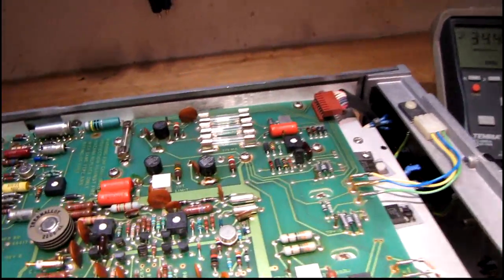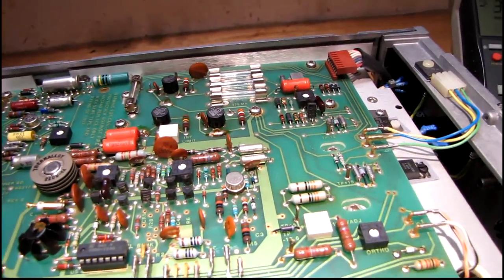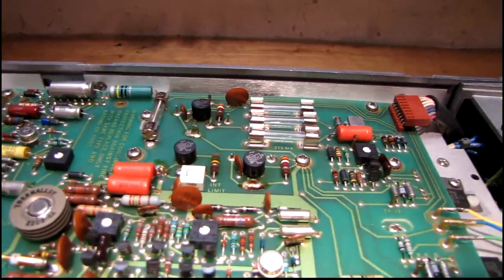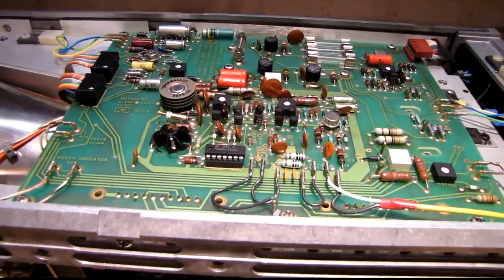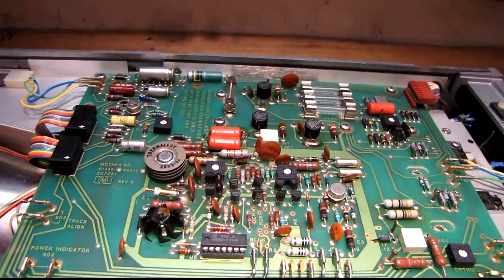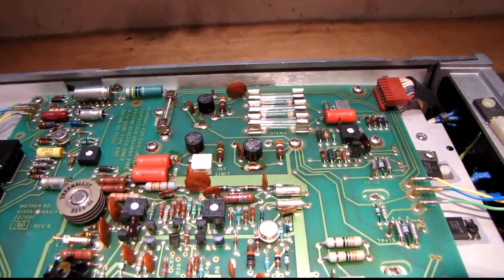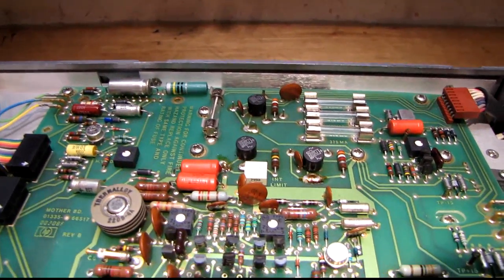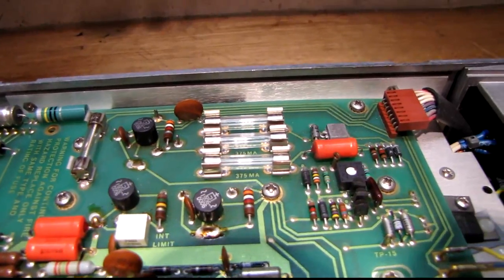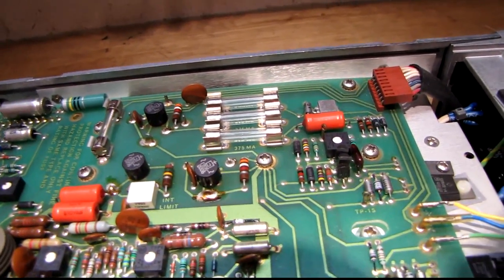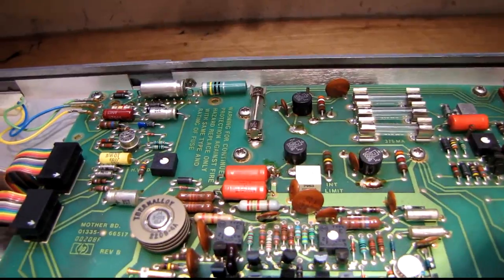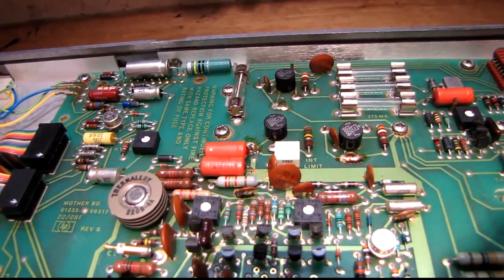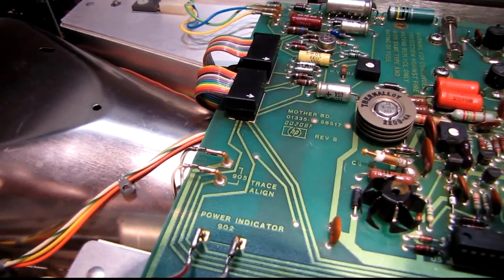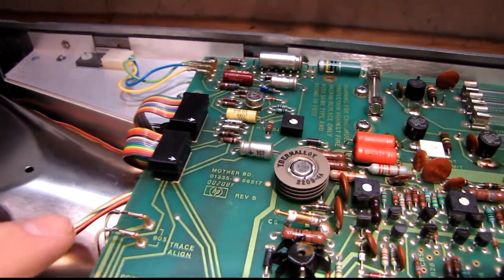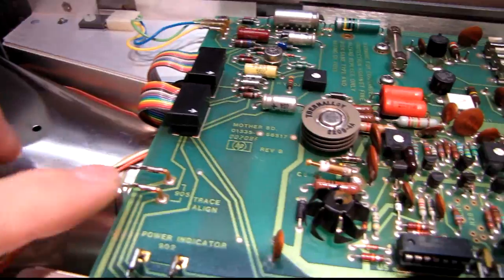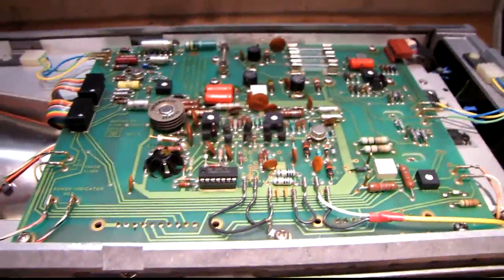Then all the fuses, I ohmed them out and they're all good, so I'm going to go a little bit farther back and take a look at these rectifiers. Well, just like I suspected, it looks like there's a couple of bad bridge rectifiers in here. I had AC voltage coming in and nothing coming out, and the fuses aren't blown, so I'm all but certain that these rectifiers have just died of old age and temperature fluctuations and stuff.